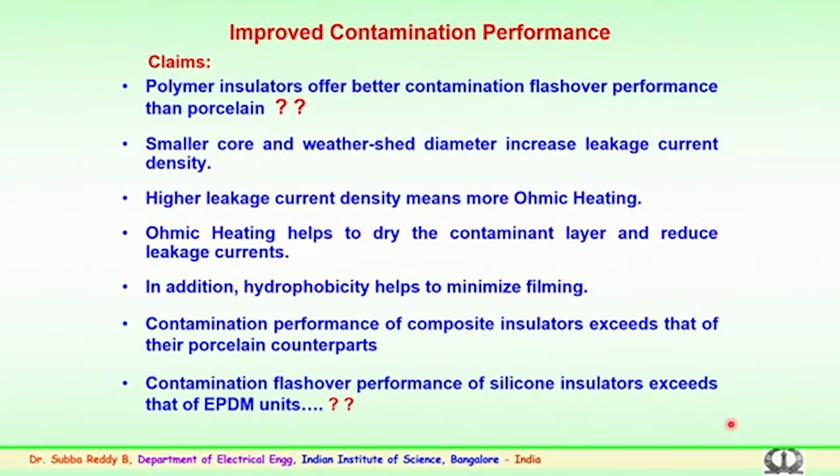Presently, as I mentioned, those being used are of third generation. So, EPDM were earlier used; how much better is the silicone, the time comparison is very important. This has to be properly verified in the laboratory from the field insulators, and the performance of the silicone can be judged, where the flashover performance could be better in comparison to the earlier EPDM units.